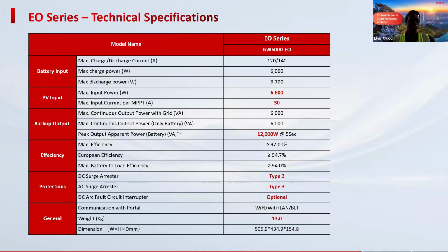Some of the important technical parameters: on the PV side, it has a maximum input current of 30. With that, it has 2 strings for that MPPT. Therefore, you are able to use any panel that has a short circuit current less than 15 amps. It also has an overload capacity of 12,000 watts, which is double its capacity. It does come with Wi-Fi and LAN. Therefore, if you want to do remote monitoring, you're able to do it.